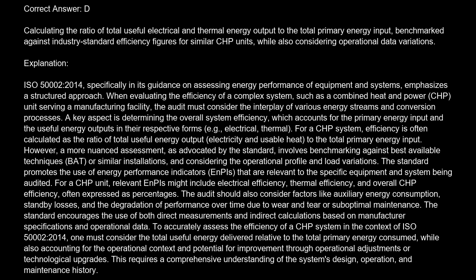However, a more nuanced assessment, as advocated by the standard, involves benchmarking against best available techniques (BAT) or similar installations, and considering the operational profile and load variations. The standard promotes the use of energy performance indicators, EnPIs, relevant to the specific equipment and system being audited. For a CHP unit, relevant EnPIs might include electrical efficiency, thermal efficiency, and overall CHP efficiency, often expressed as percentages. The audit should also consider factors like auxiliary energy consumption, standby losses, and the degradation of performance over time due to wear and tear or suboptimal maintenance.